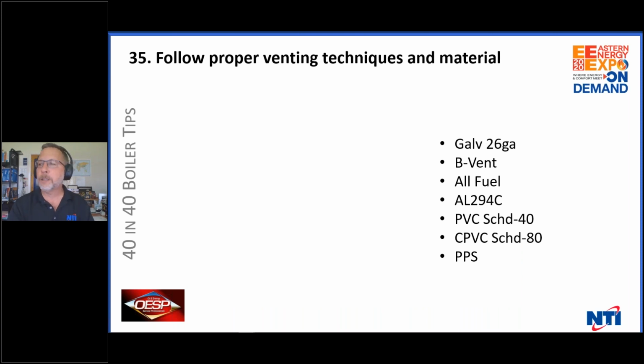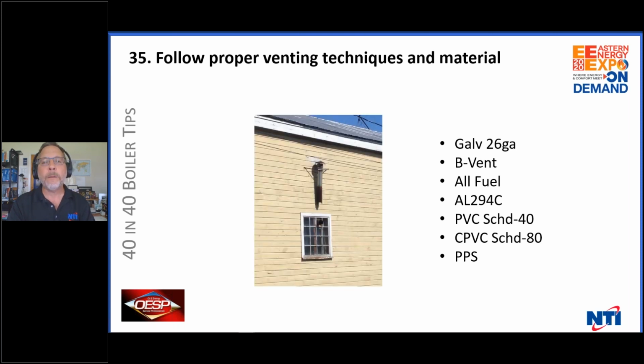RTFM first, folks. If it needs galvanized, use galvanized. If it's a condensing boiler, don't use it. B-vent on atmospheric gas, all fuel for your oil fired. AL294C works for condensing in some of your copper fin tube. PVC Schedule 40, which will soon probably be taken out of the code. CPVC Schedule 80 fire rated, and polypropylene. Know it, because things like this just don't pass muster anymore.